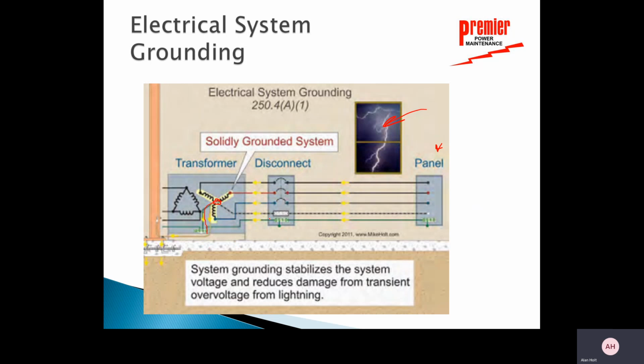But notice again, even here's my disconnect. My disconnect is not connected to ground right there. That's a separately derived system. It's only connected to ground right here at the transformer in this location. So this would be like an industrial setting where I'm inside.